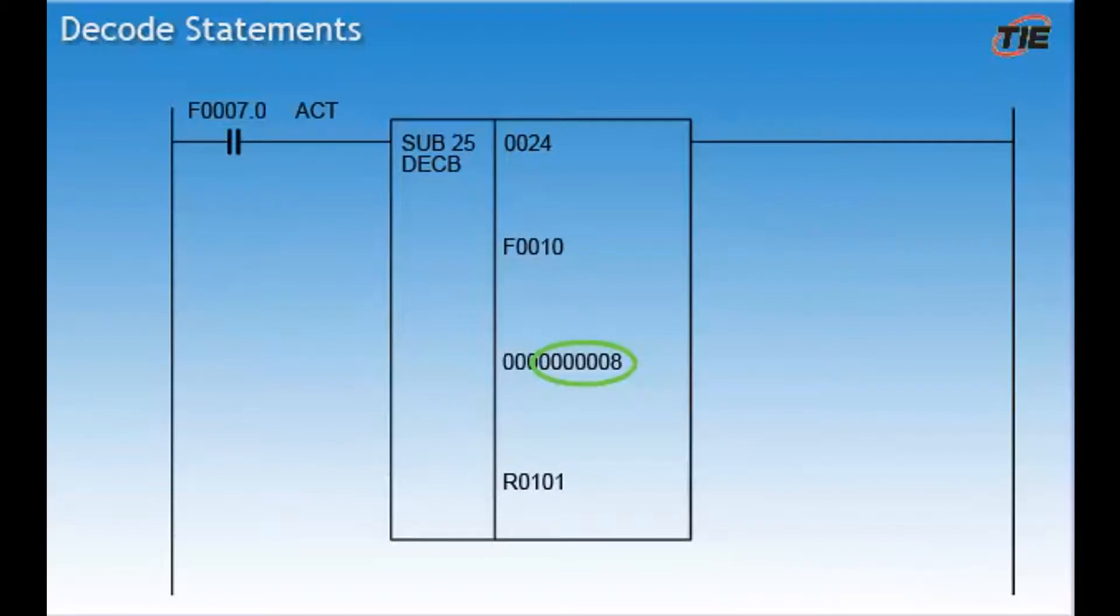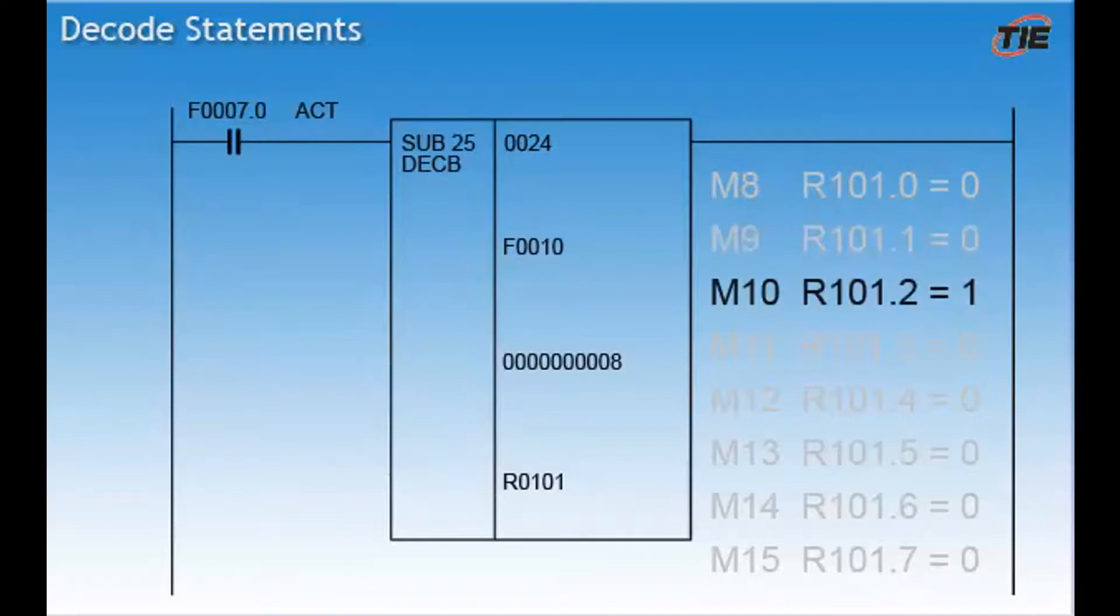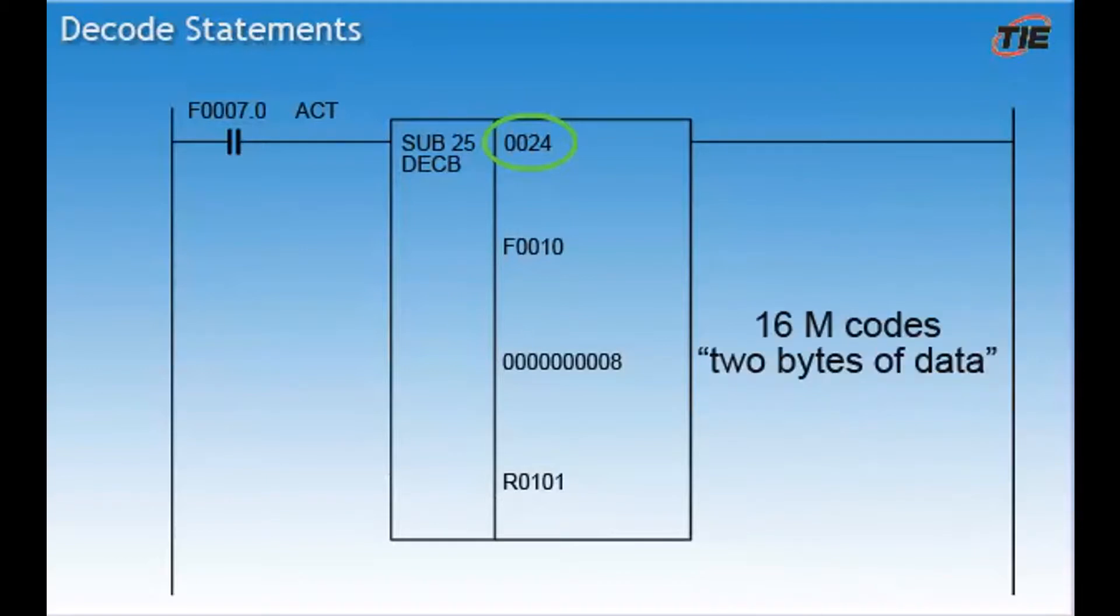Here is an example. The starting address for the M code statement is M8. A call of M8 will turn on R101 bit 0. A call of M9 turns on bit 1, M10 turns on bit 2, and so on. In the example used earlier, you will see that this number is set to a 2. This means that this decode statement handles 16 M codes. The starting address is 8, so this decode statement will handle M8 through M23.